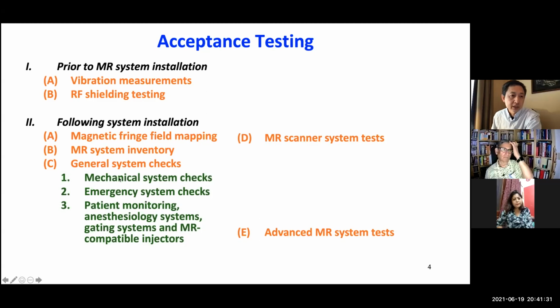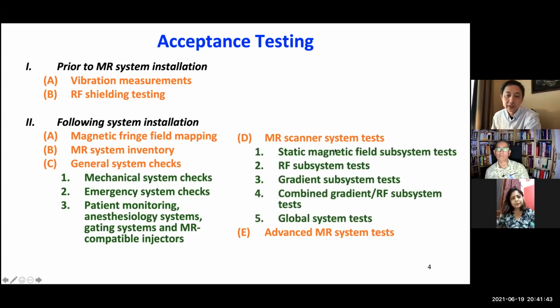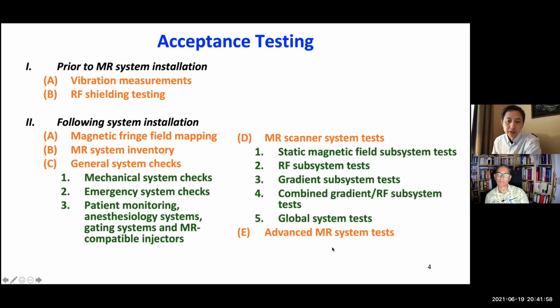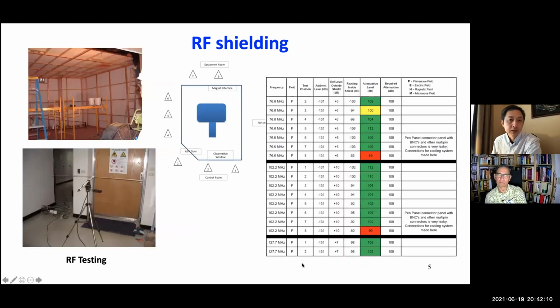So some details about general system checks. We check the mechanical system, emergency system, patient monitoring, and other third-party equipment. For the MRI system testing, the scanner itself, we test the static magnetic field, RF field, the gradient subsystem, and also the combined gradient RF subsystem, and global overall quality. And for advanced MRI testing, typically that includes ultrafast imaging like EPI and spectroscopy tests.